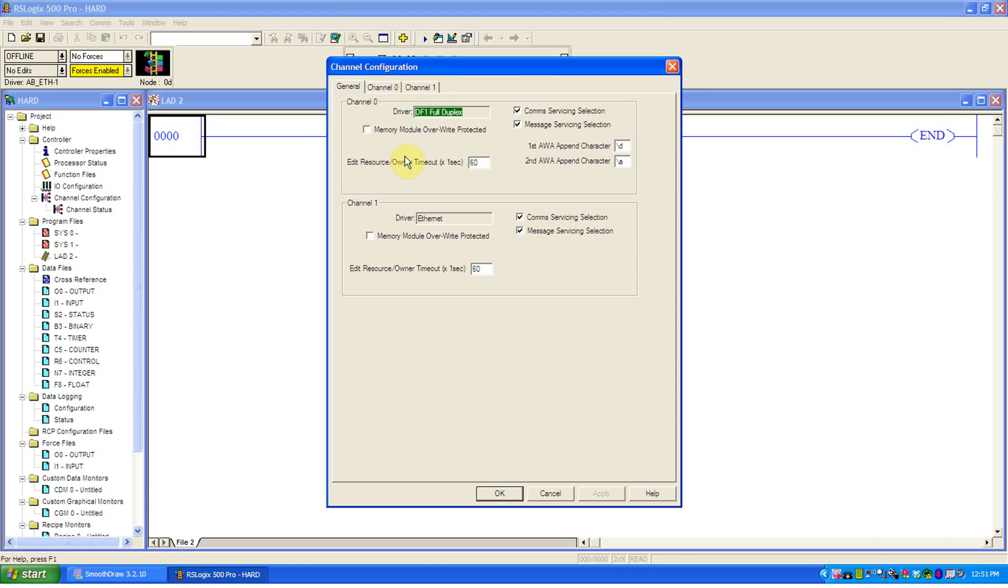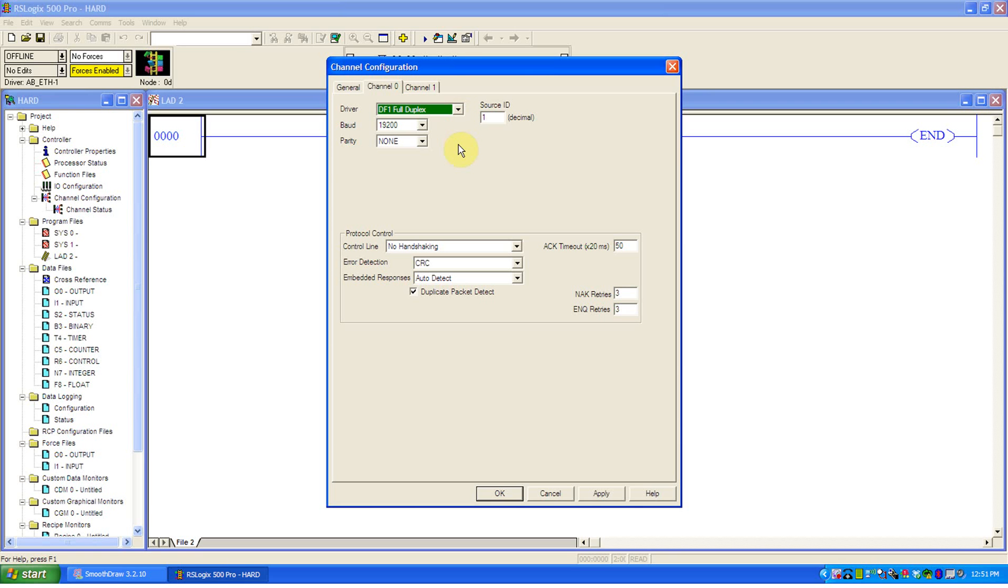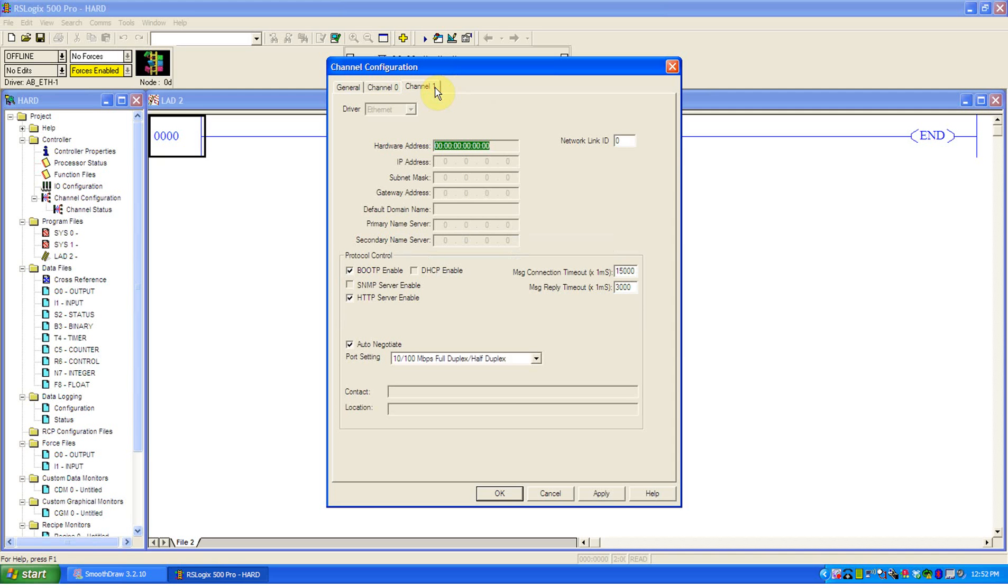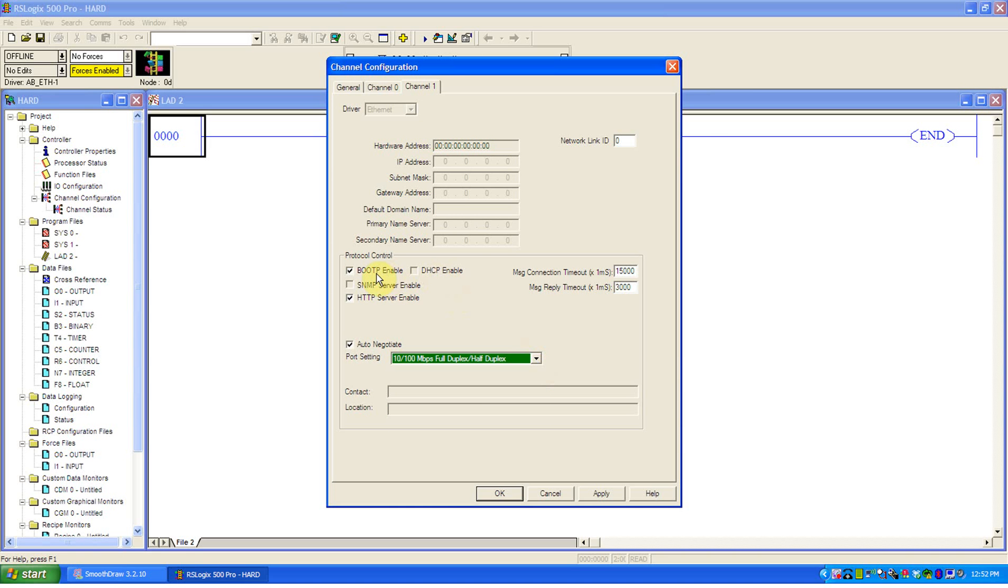If you come in here there's a general screen that shows you channel 0 and channel 1. Channel 1 is Ethernet. Channel 2, you have a few options but it's set up default for 232 which is serial communications. You'll see here you can set up the communications protocol and type. This is where I say there's a whole bunch of different options for channel 0. Channel 1 is always Ethernet. It has to be Ethernet. This is how we're talking with it. We can change some of the Ethernet settings. But the problem is actually right here. That it wants to run what's called a BOOTP server.